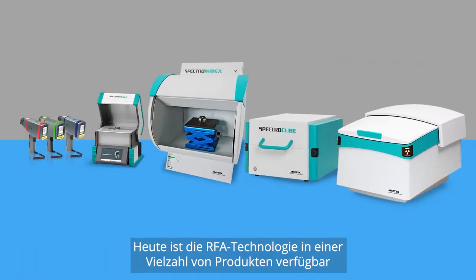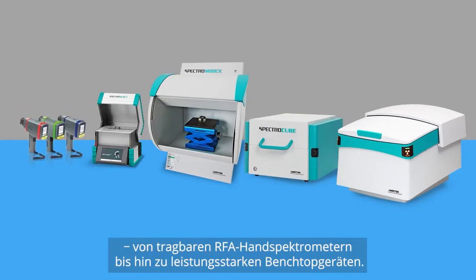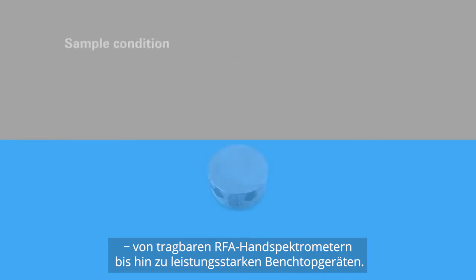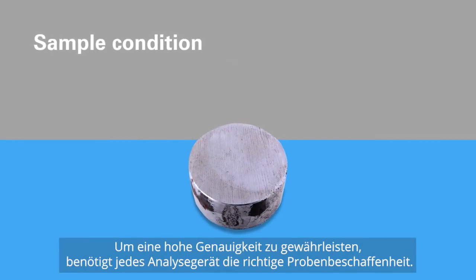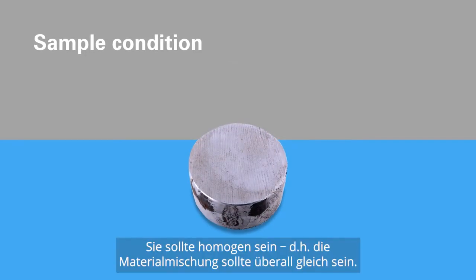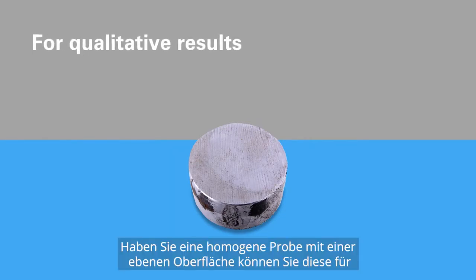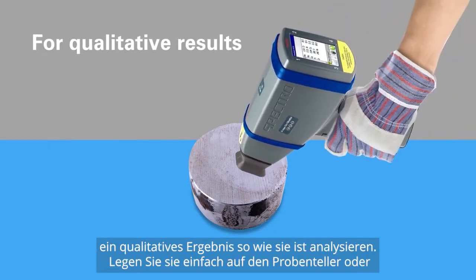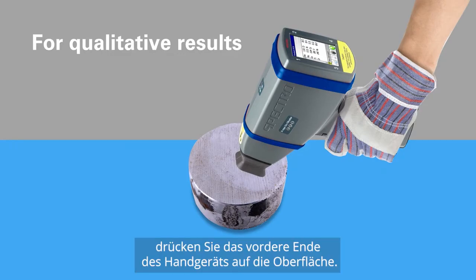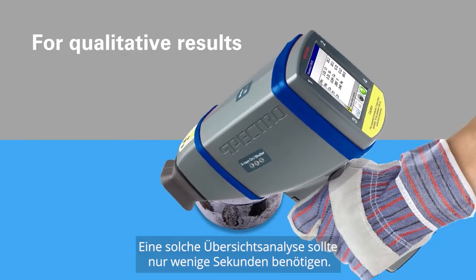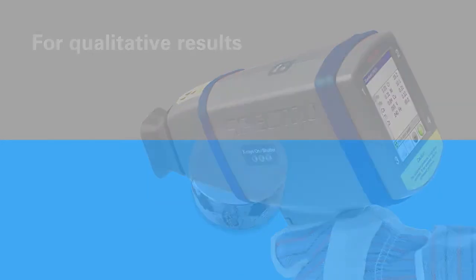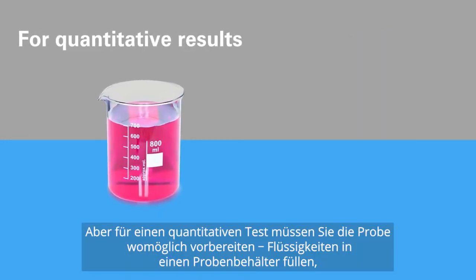Products range from portable handheld XRF guns to high-performance benchtop analyzers. To ensure accuracy, any analyzer needs the right sample condition — it should be homogeneous, meaning the same mixture of material throughout, and it should be representative of the material you're trying to analyze. For a qualitative result, if you have a homogeneous sample with a flat surface, you can test as-is: just place it in the sample tray or press the nose of the handheld unit to the surface. This screening analysis should take only a few seconds.